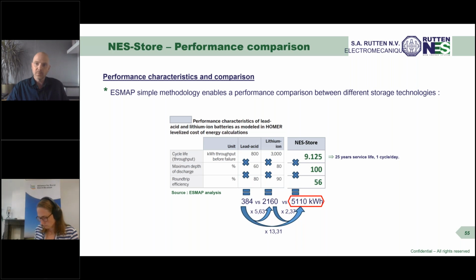This partly explains why lithium has been increasingly preferred to lead-acid batteries, despite being more expensive in terms of initial investment. If we make the same comparison with the NES-Store, assuming a 25-year service life, this suggests that with 5,110 kilowatt-hours, it should be more than 13 times more performant than lead-acid batteries and more than 2 times more performant than lithium-ion. Unfortunately, performance is not everything, and being more performant does not necessarily mean being the best. Next slide, please.